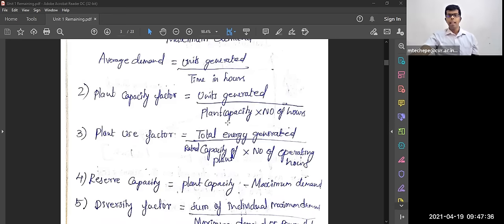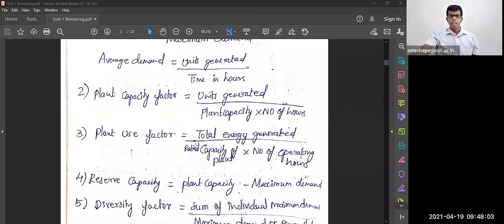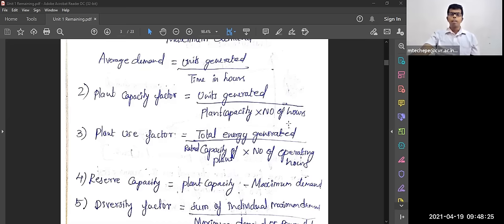Plant use factor is equal to total energy generated divided by (rated capacity of the plant × number of operating hours). For number of operating hours, we generally take 24 hours for daily analysis, 24×30 for monthly, and 24×365 for yearly.